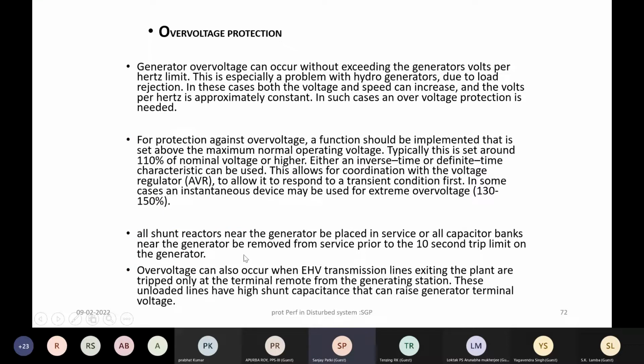Similarly, the coordination of over voltage protection of the line. Normally the over voltage protection is set at 110% with some time delay, and for extreme over voltages to the tune of 130% or so, instantaneous tripping has been provided. So there is a two-stage over voltage protection, and this over voltage protection again, as I explained, can be one of the protections causing undesirable tripping due to over voltages taking place due to mismatch of reactive power demand and the reactive power supply. You may face over voltages, and you may lose the lines due to over voltage protection.